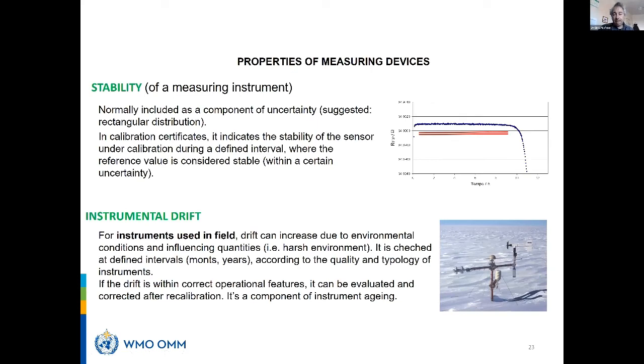The stability, well, let me say that we use this term more in the laboratory to say how stable the instrument is during the calibration when it is exposed to a constant stimulus, as we call it. So to make it short, I have a very stable temperature bath. I have a very stable length standard. I measure the length with the laser, I measure with the thermometer the temperature, which is stable. And despite my temperature being stable at the millikelvin level, the resistance of the thermometer has some noise. So this is a stability.